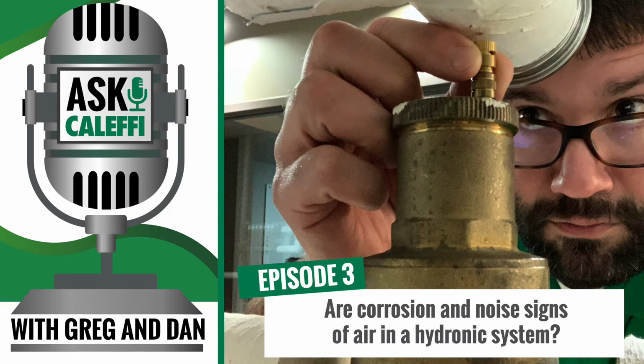Exactly. You kind of hit it right there with the larger body. What we find is that our air separator bodies can be 3 to 4 times bigger than the pipe connection size coming to them. And that's so you get an instant velocity drop. Right. That wider body will reduce velocity up to about a 10-to-1 ratio. Yeah. And that really allows that coalescing mesh to knock those micro bubbles loose from the water.